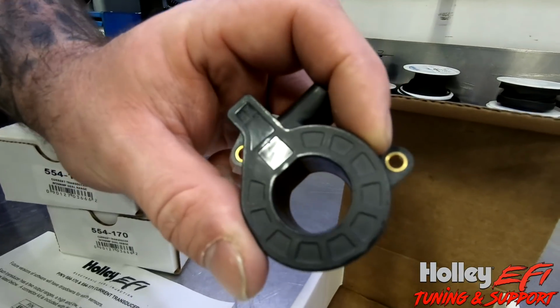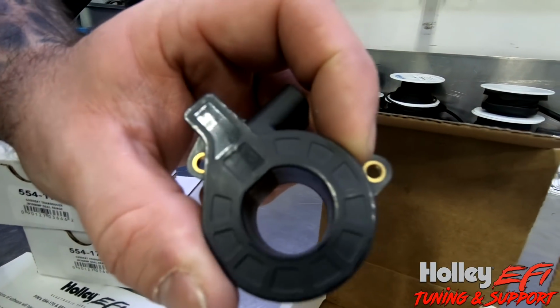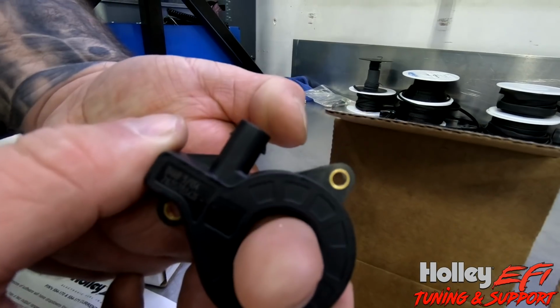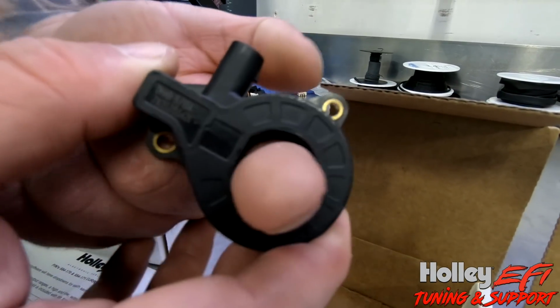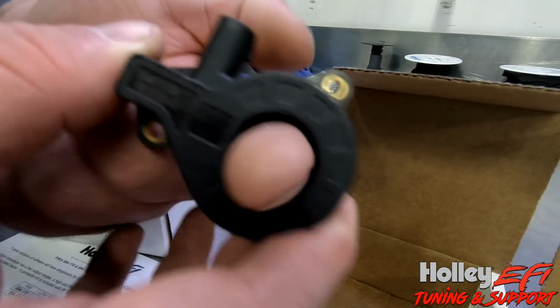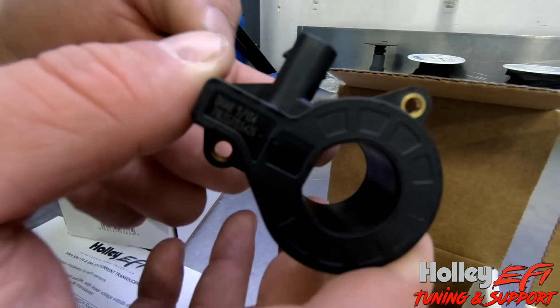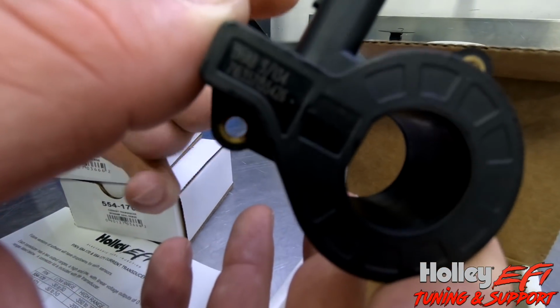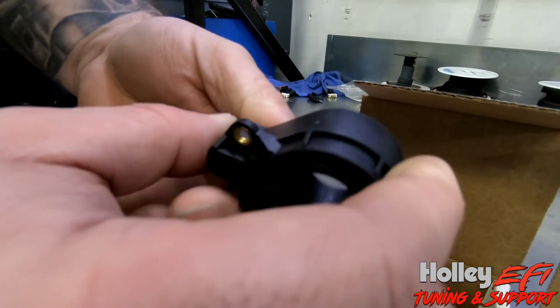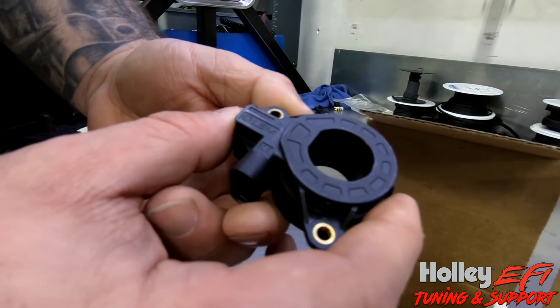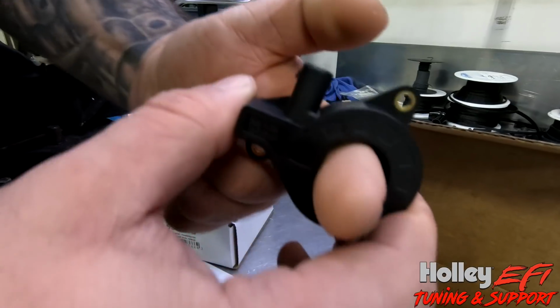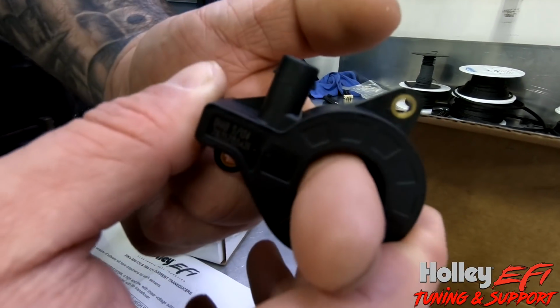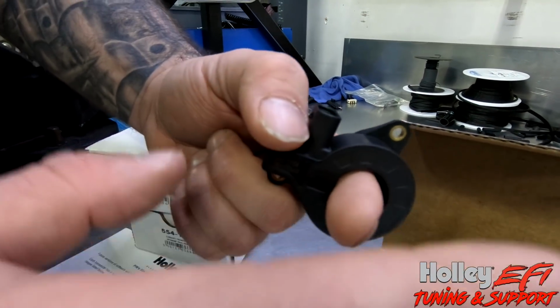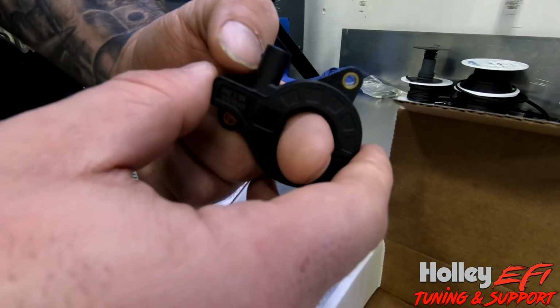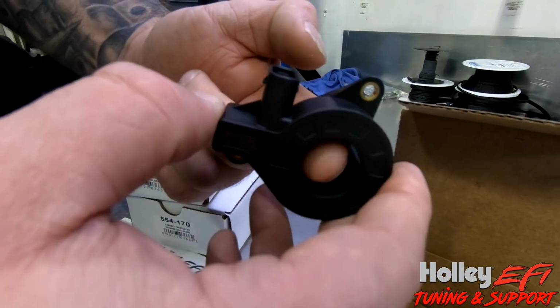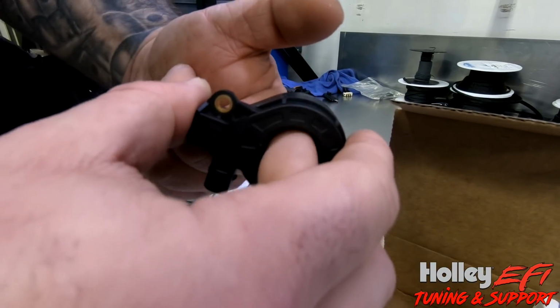The transducers are pretty straightforward. There's a hole in the middle, so you shove the wire through the hole. These are plus and minus, so they're directional, depending upon how you have it mounted on the wire, it will give you a negative or a positive reading. If the wire is coming in this way and you're drawing amperage on this side, you'll get one reading; if you flip it over, you'd get a negative reading.